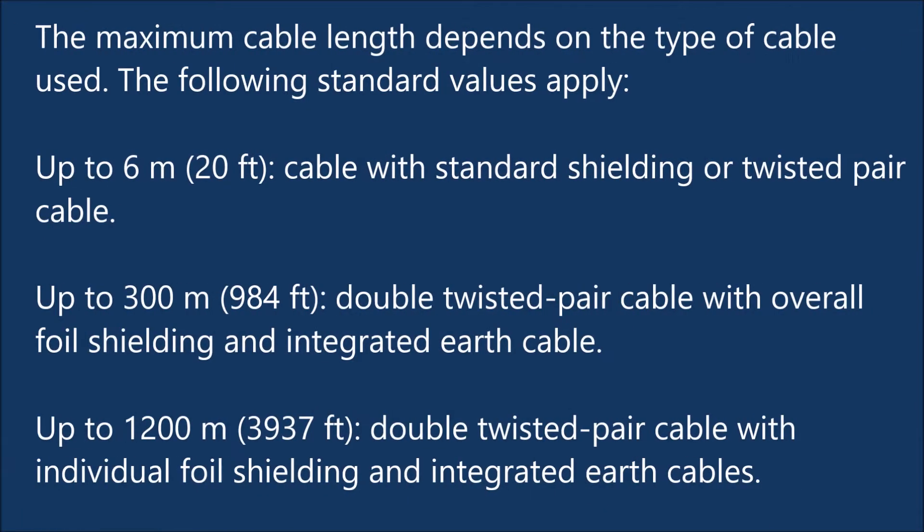The maximum cable length depends on the type of cable used. The following standard values apply: up to 6 meters (20 feet) with cable with standard shielding or twisted pair cable; up to 300 meters (984 feet) with double twisted pair cable with overall foil shielding and integrated earth cable; up to 1,200 meters (3,937 feet) with double twisted pair cable with individual foil shielding and integrated earth cables.